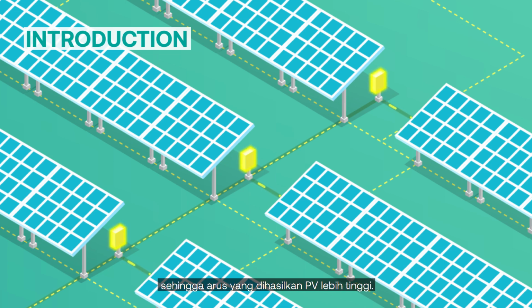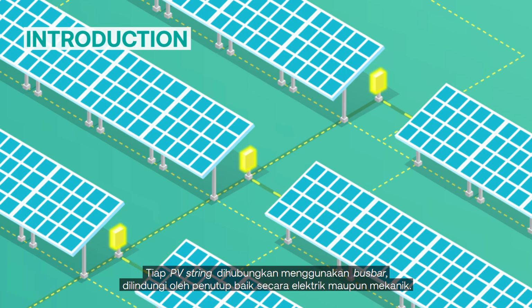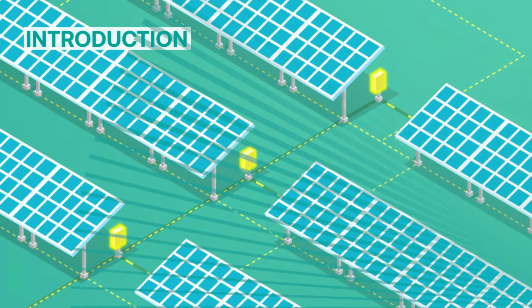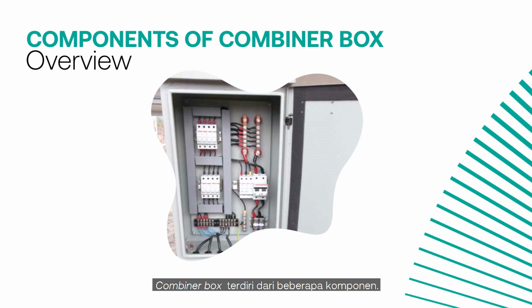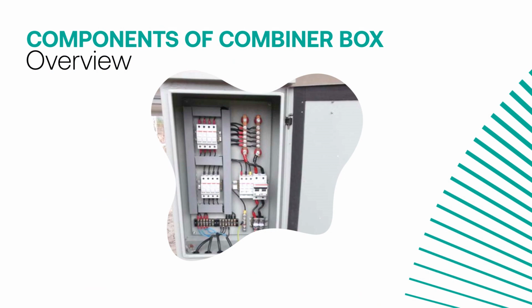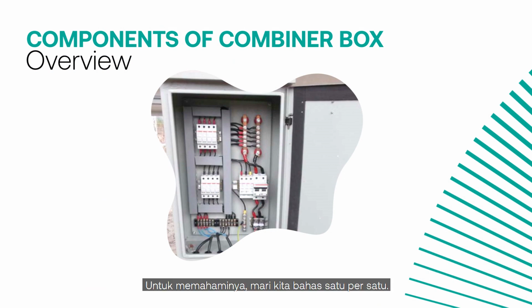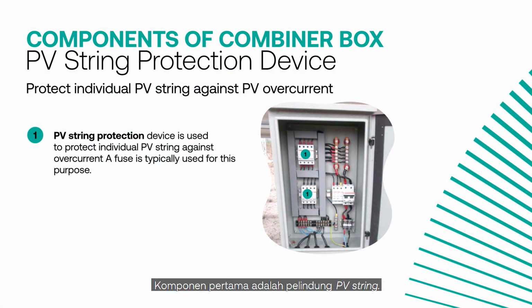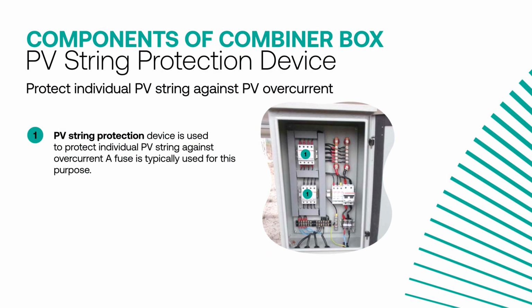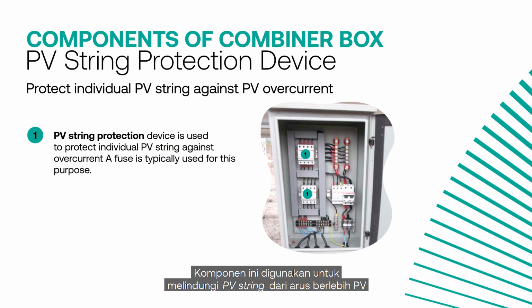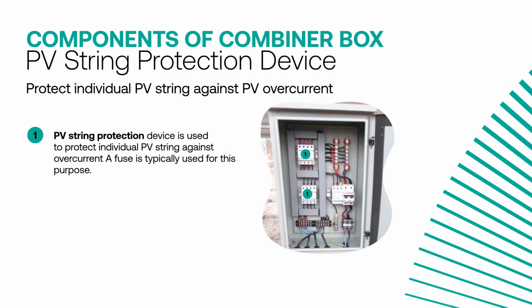output current is obtained. Individual PV strings are connected using bus bars and both electrically as well as mechanically protected inside an enclosure. A combiner box comprises several components. To understand them, let us discuss each of the components. The first component is the PV string protection device. A PV string protection device is used to protect an individual PV string against PV overcurrent. A fuse is typically used for this purpose.